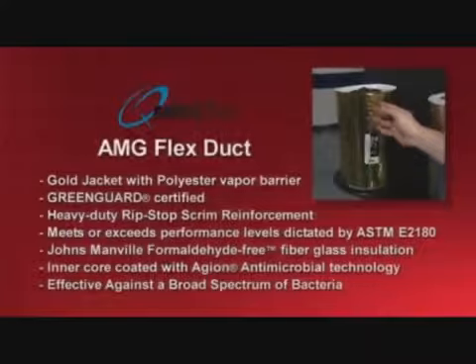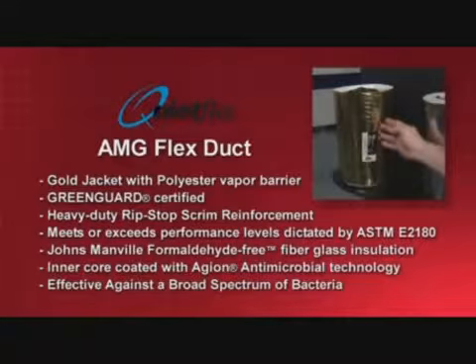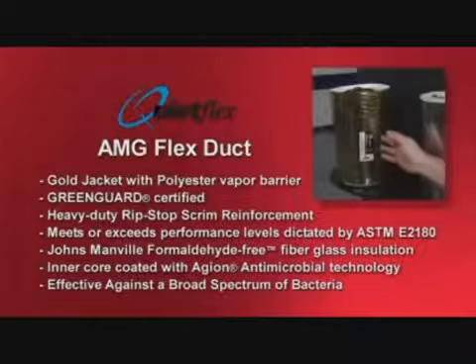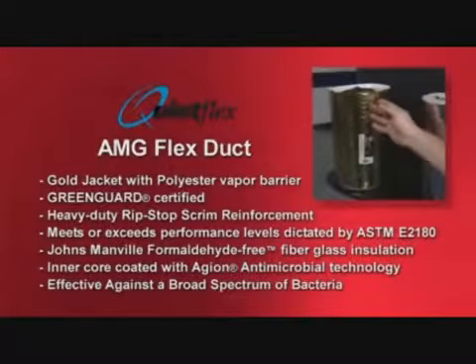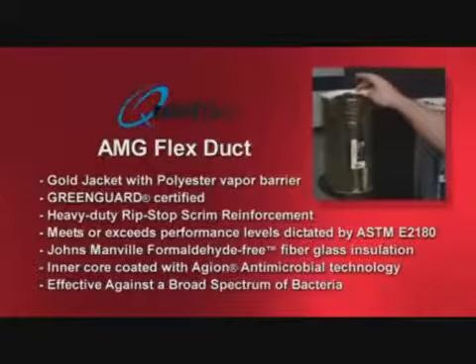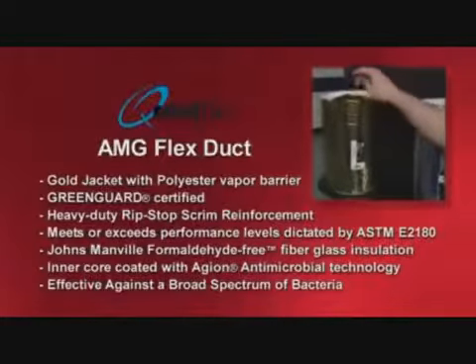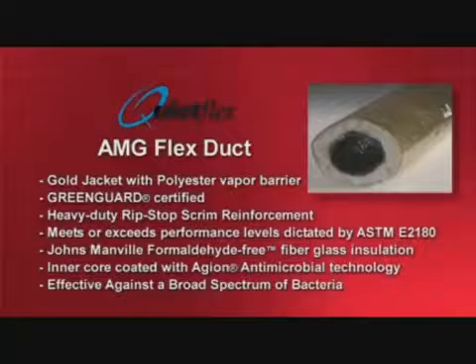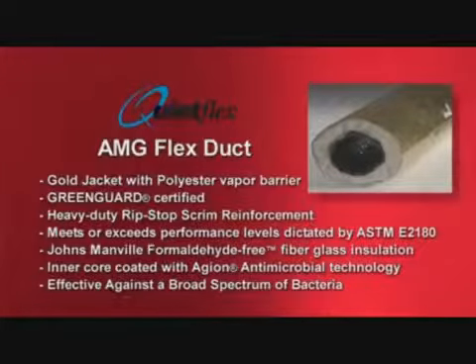Our AMG Flex is a new product out recently. It has, again, a heavier duty jacket compared to the silver jacket, has the scrim inside the jacket, and then we also have the formaldehyde-free fiberglass, oversized core, and the mil galvanized wire for the reinforcing. The thing that's unique about this product as well is it also has an Agion-coated core so that it inhibits mold and bacteria growth, cutting down on odors and etc.